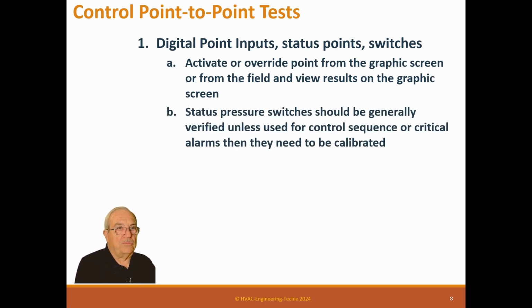Status pressure switches should generally be verified unless used for control sequences or critical alarms, then they need to be calibrated. So let's say you've got an air handler with a filter pressure switch and another pressure status point on the supply duct, and to tell you the truth, those probably don't need to be calibrated. If they're off 10 or 15%, it probably makes no difference. But if you're actually doing pressure control of a system, that one you need to calibrate. So you need to be smart about what you're doing. And when we come to digital points, you can override those several ways.